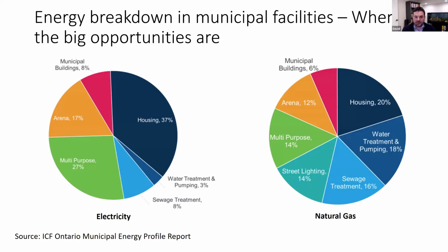They use a lot of energy - in fact, up to 12% of the natural gas and 17% of electricity in a municipality. To put this in perspective, housing is 20% of an average municipality's energy use. So this is a real opportunity, because one of the byproducts of refrigeration is heat, and natural gas is used for heating arenas. By utilizing the waste heat from the refrigeration system, these facilities can be a big part of the climate initiatives everybody has right now.